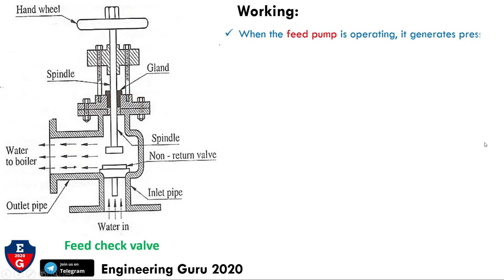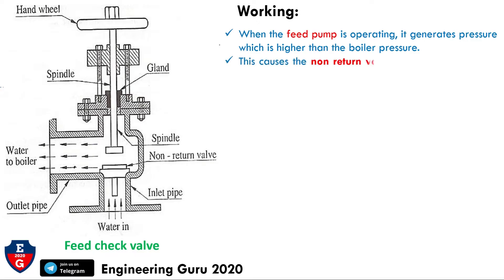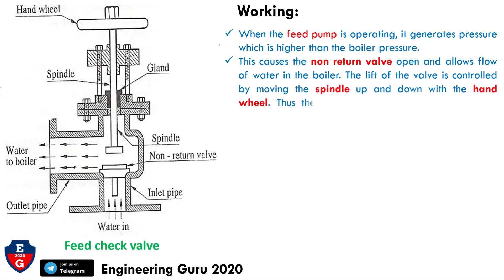When the feed pump is operating, it generates pressure higher than the boiler pressure. This causes the non-return valve to open and allows the flow of water into the boiler. The lift of the valve is controlled by moving the spindle up and down with the hand wheel, thus controlling the flow of water to the boiler.